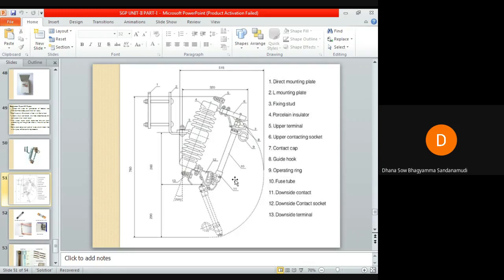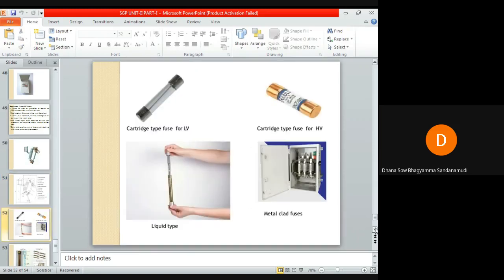The only thing we have to remember is that there will be a fuse link chamber, that is the fuse tube here, and whenever an arc is struck here under fault condition, that arc will be deionized by the boric acid, which decomposes into water vapors, and these water vapors deionize the arc path, preventing the arc from restriking. Boric acid expulsion power fuses are further divided into refillable and replaceable fuses. This is not required as per syllabus, but I have included it to give a brief introduction.